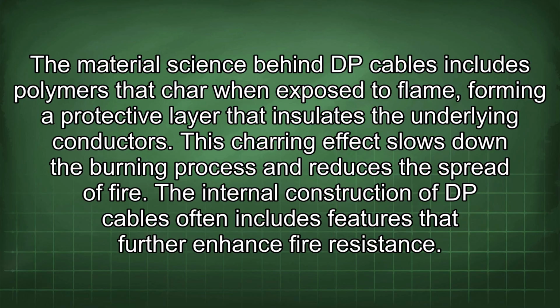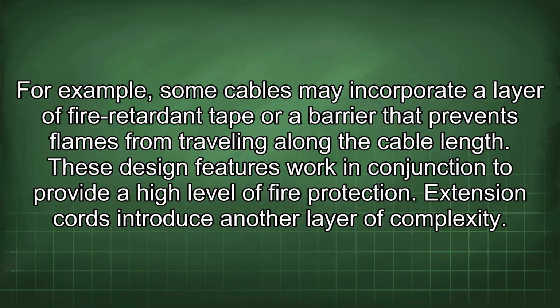The internal construction of DP cables often includes features that further enhance fire resistance. For example, some cables may incorporate a layer of fire retardant tape or a barrier that prevents flames from traveling along the cable length.